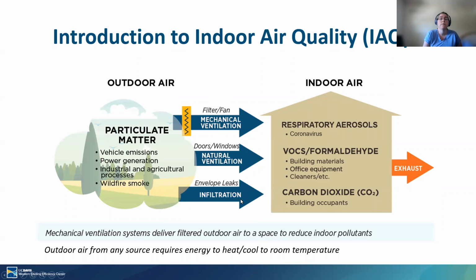The first one is infiltration through the envelope. So our building envelopes have all kinds of leaks and cracks in them. And as the building code has been updated throughout the years, the building tightness has increased. So older buildings tend to be more leaky. We have natural ventilation, meaning we can open doors and windows. And then we have mechanical ventilation, which uses a fan to pull air from outside to inside.